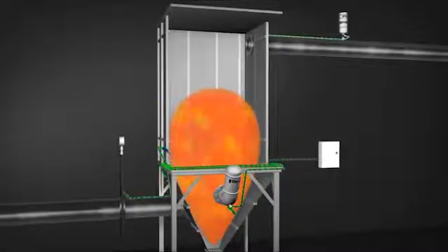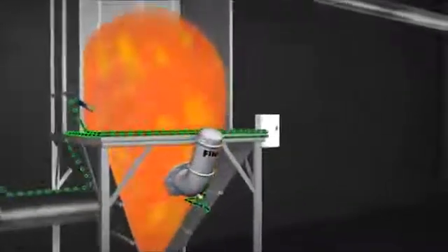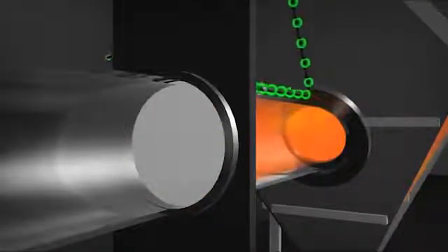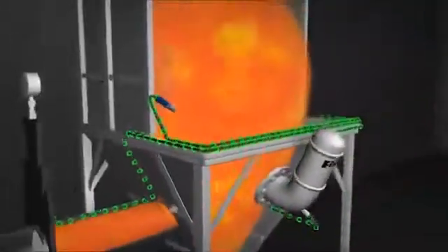The gas cartridge actuator drives the piston on the isolation valve, closing the slide gate, and provides mechanical isolation which prevents the propagation of the explosion through the ductwork to interconnected vessels.